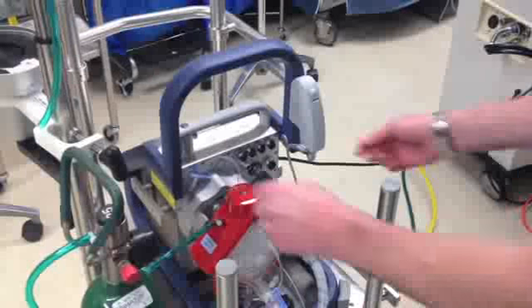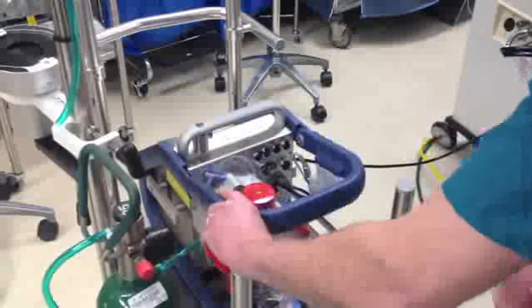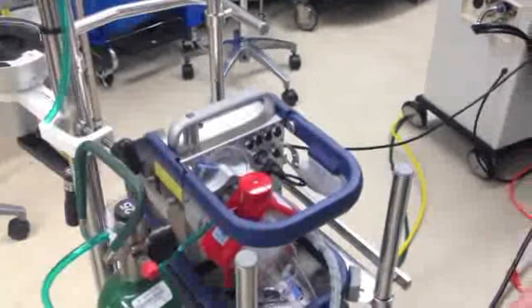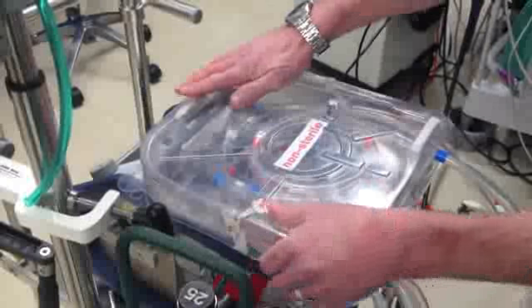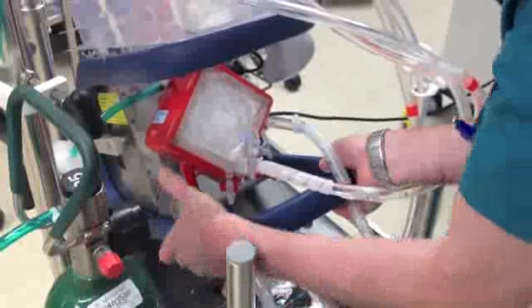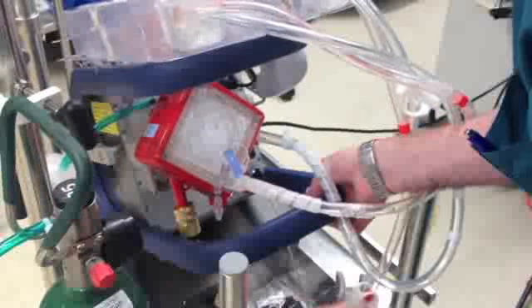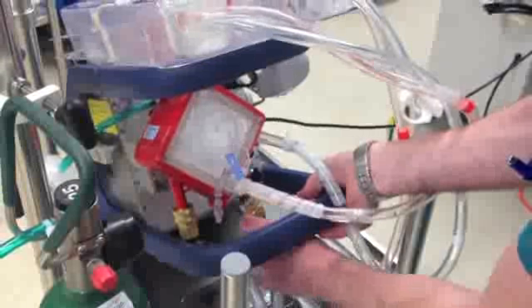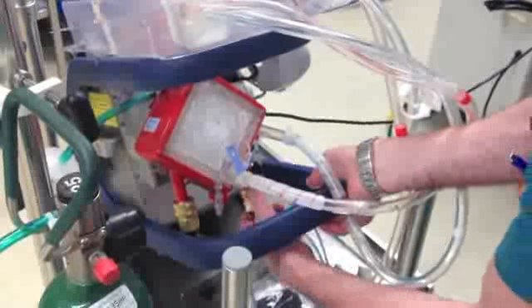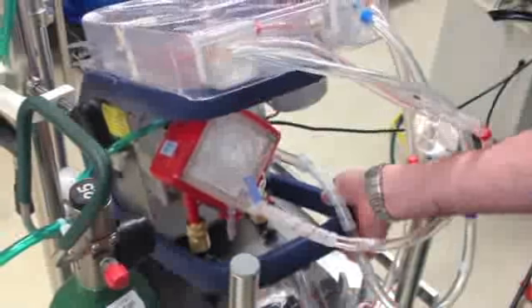Then you disconnect the integrated sensor and connect it to the HLS set. And then you close the guard, which you only have to push 1 button to close. And you'll attach the table tray directly to the top handle there. It's designed to do that. It'll sit right on there. And then another unique aspect to our procedure or our steps are that we connect the water lines now. And it doesn't matter which side you connect them to as long as you hear the click and they're seated on there tight. Those are just quick connectors, pretty simple.